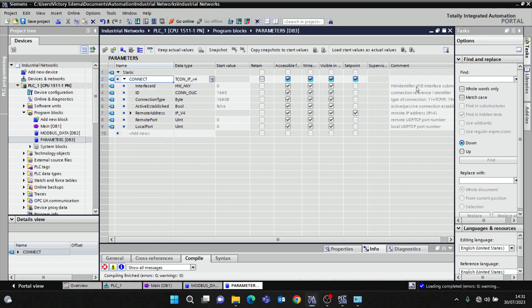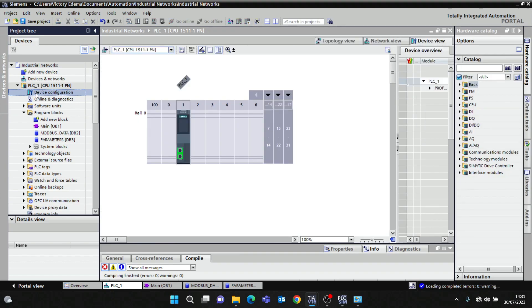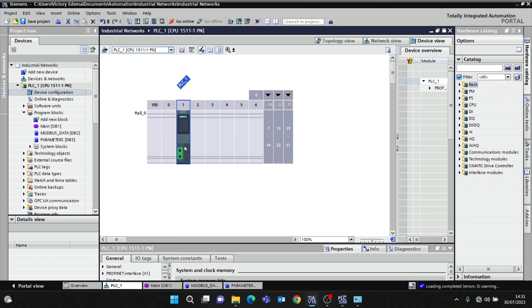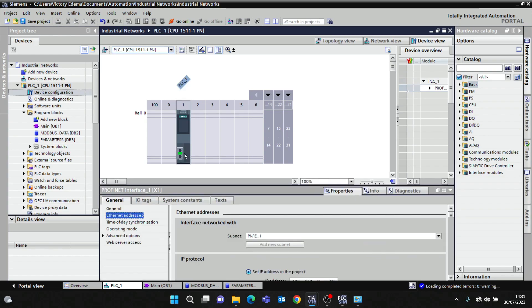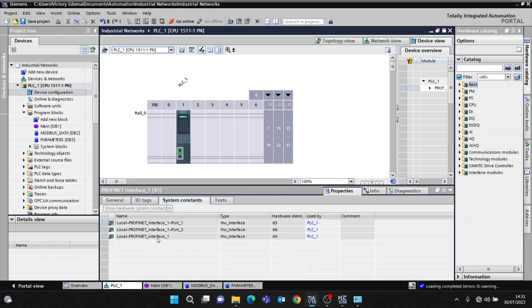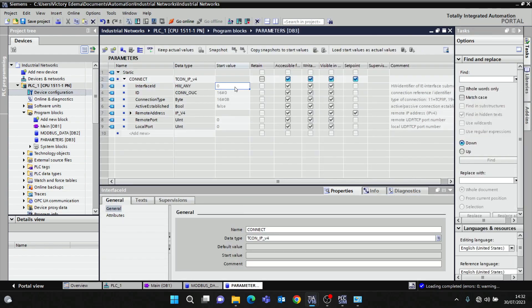This is going to bring out the connection parameters. Interface ID means what is the hardware identifier of the Ethernet interface. Head up to device configuration, click here on the Ethernet port, come to system constant. It says local ProfiNet interface ID 64. HW_INTERFACE is 64, so I'll come back to parameters and put 64.